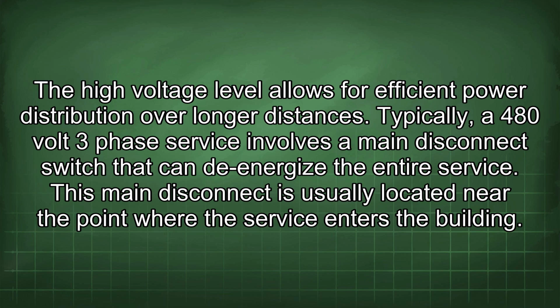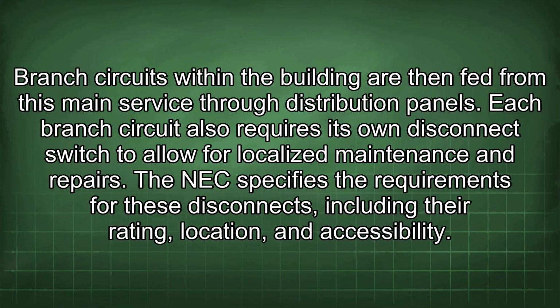Typically, a 480-volt three-phase service involves a main disconnect switch that can de-energize the entire service. This main disconnect is usually located near the point where the service enters the building. Branch circuits within the building are then fed from this main service through distribution panels. Each branch circuit also requires its own disconnect switch to allow for localized maintenance and repairs. The NEC specifies the requirements for these disconnects, including their rating, location, and accessibility.